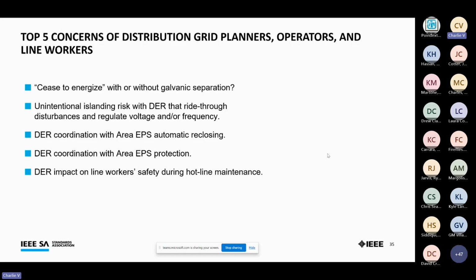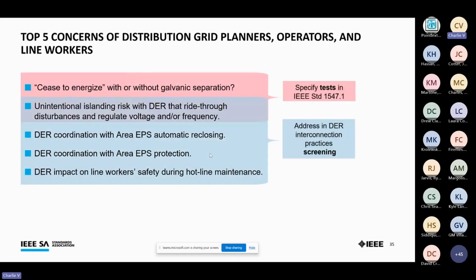The other aspect is that 5 minute return to service. There's more language in 1547 2018 that allows, with agreement with the connecting utility, that time to return to service to be shortened. There's a lot of concern as you start getting these DER that are riding through brief events. A lot of consideration, but still concern, that the distribution system protection schemes that let these DER ride through short-term grid events don't interfere with the protection schemes in place by the utility at distribution, subtransmission, and transmission. So there's some consideration of that present in the timeframes around ride through.